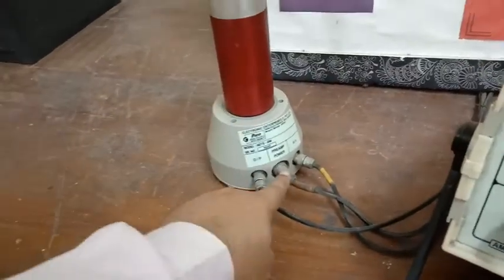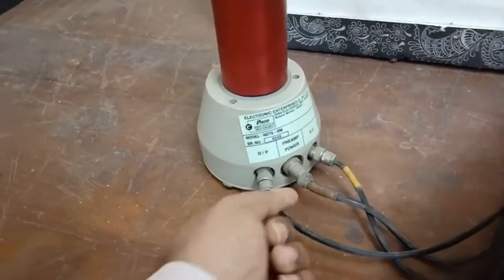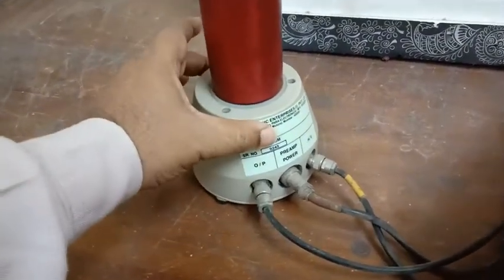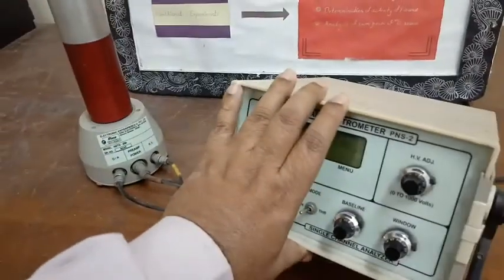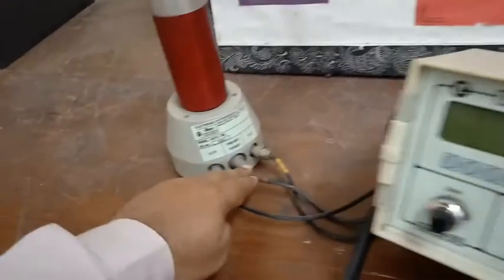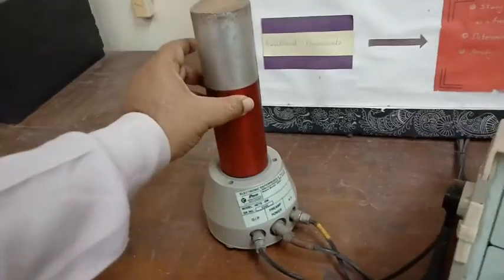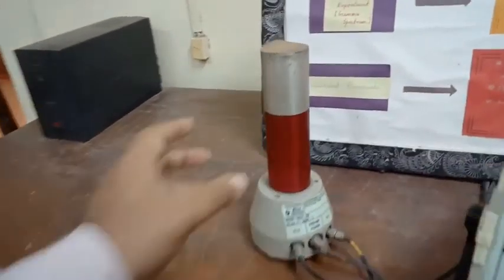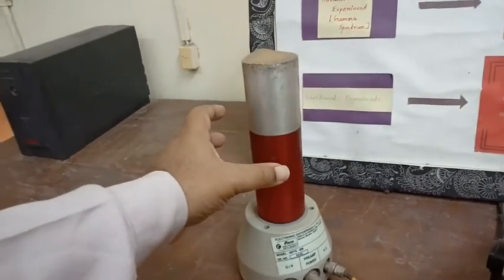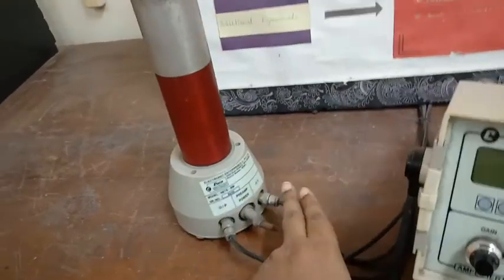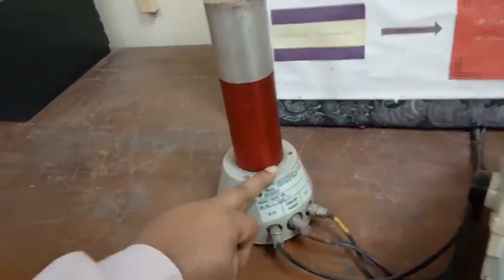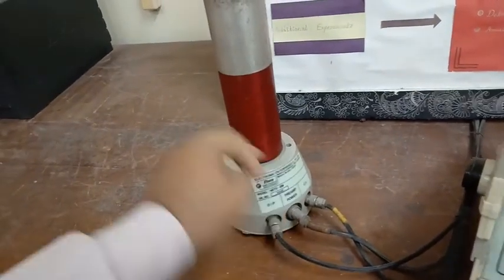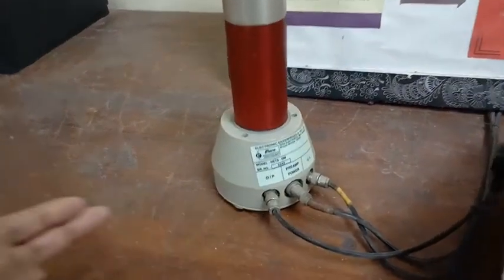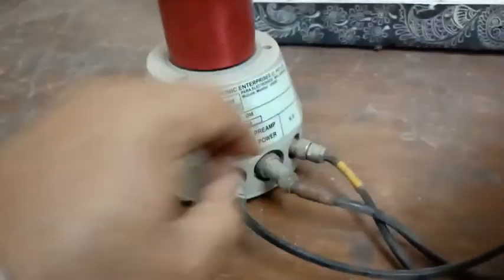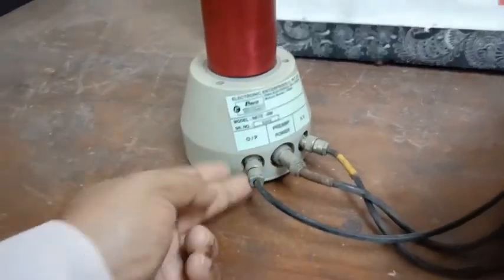Now the second cable here is the one for the preamplifier power. The preamplifier needs some power, and this is also given by this setup. For the detector setup, sodium iodide, to work we also need a high voltage supply, and this supply is given by this unit as well. So this is the input for the high voltage, this is the input for the preamplifier, and this is the output from the preamplifier. So three cables, and these are all BNC type cables, okay.